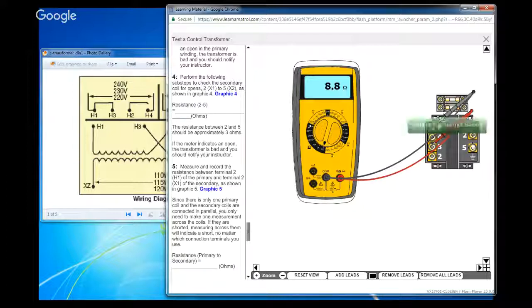That doesn't always tell you, because you could have a partial short in your secondary and you wouldn't know what that value was unless you hooked it up and checked the voltage, because that's another check. You can check the voltage coming out of it. If it's hooked up correctly, you should be reading 120 volts, however the configuration is. If you're not reading 120 volts with the fuse pulled, then it's a good bet that something's wrong with your control transformer. So that's a good thing to check. But let's look at a real one that is damaged.